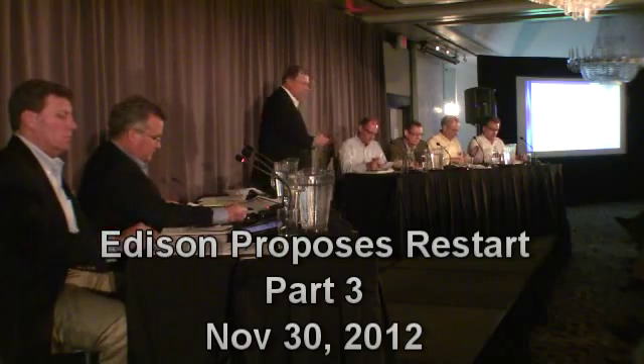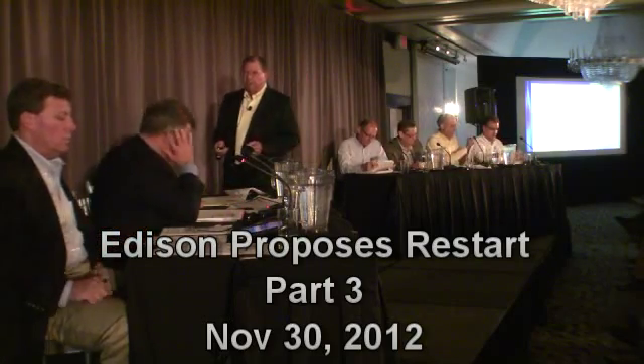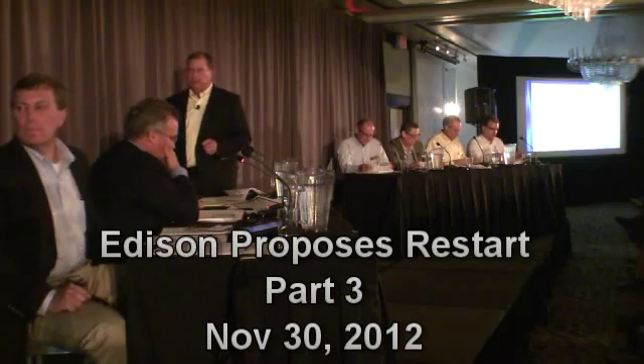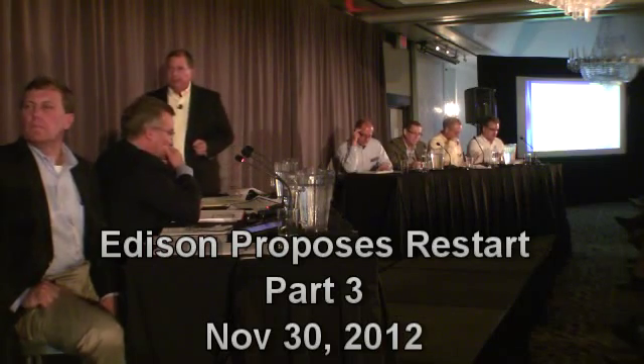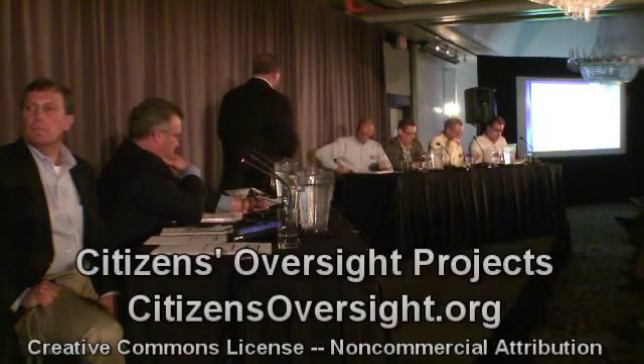Okay, so let me move on to corrective actions. So preventing fluid elastic instability, we've talked quite a bit about the role at 100% power, the velocity of the fluid, that's what transfers the energy to the tube. We've also talked about you need to improve tube damping. And this is a function, here's where the support structure comes into play.